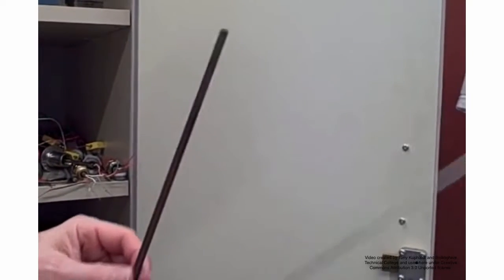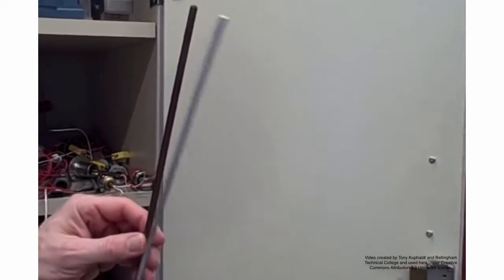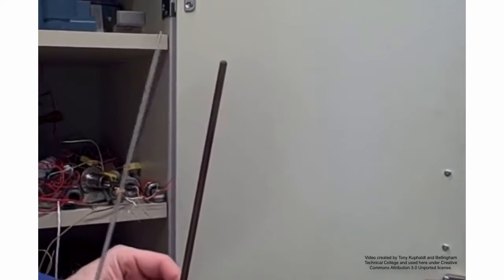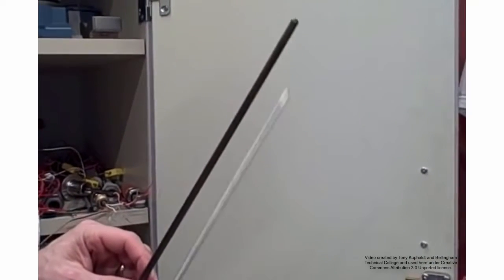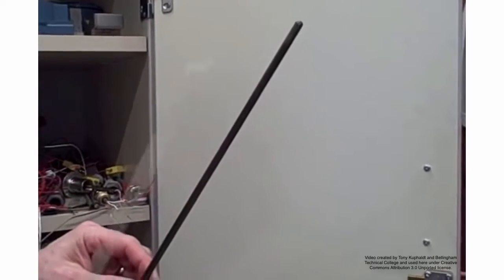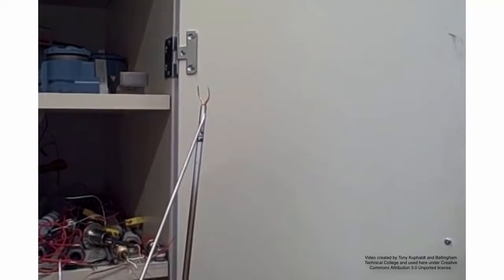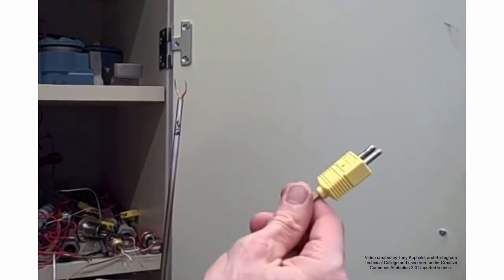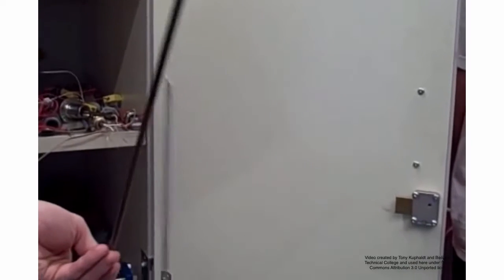Now the question was asked earlier, can we tell if this is grounded or ungrounded? You cannot tell that visually. You can only tell that with a meter. The difference between a grounded and ungrounded thermocouple is internal, and you cannot see it without cutting it open. We would have to take an ohmmeter and measure for continuity between either one of the wires and the stainless steel sheath in both cases.